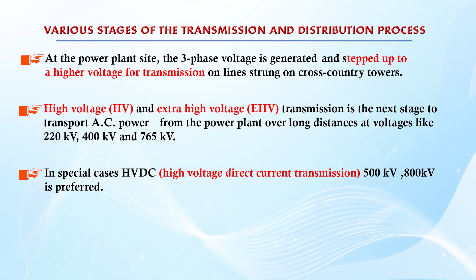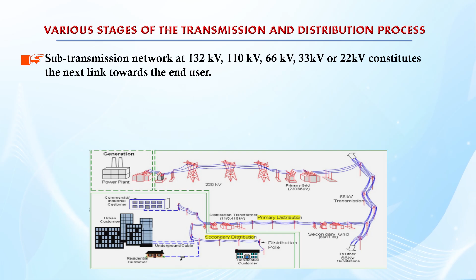Among this you will also see the sub-transmission network. Sub-transmission network means voltage somewhat less than the high transmission network, at 132 kV, 110 kV, 66 kV, 33 kV, 22 kV. This constitutes the next link towards the end user, meaning we step down the voltage.